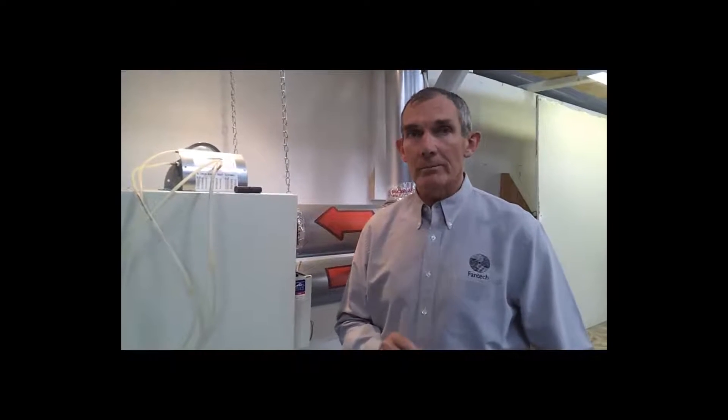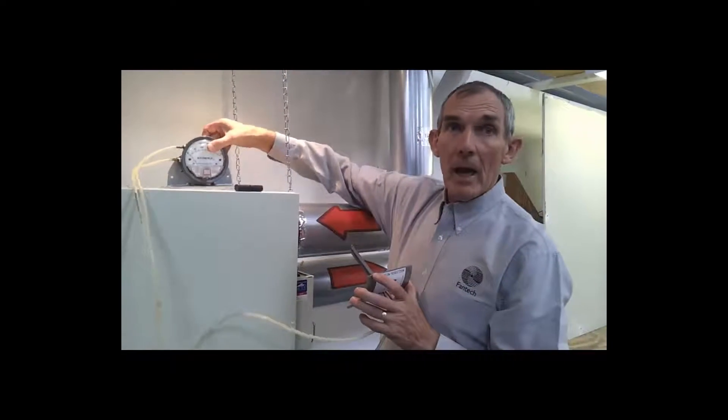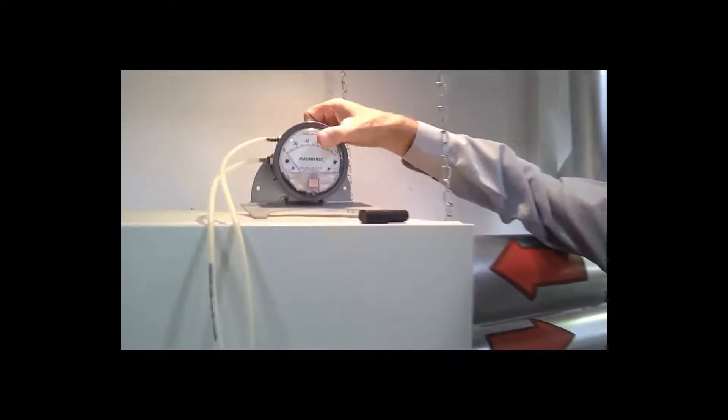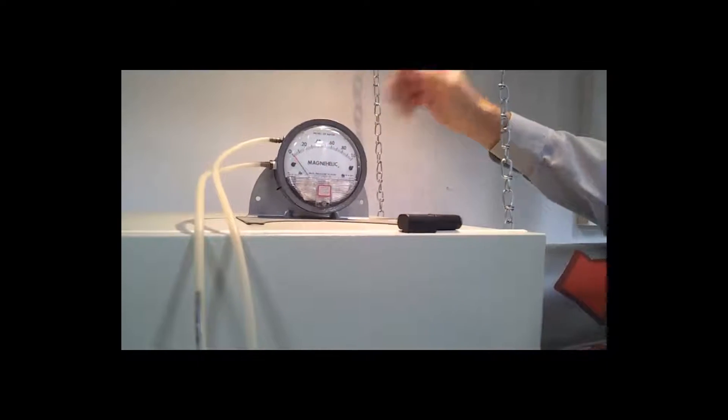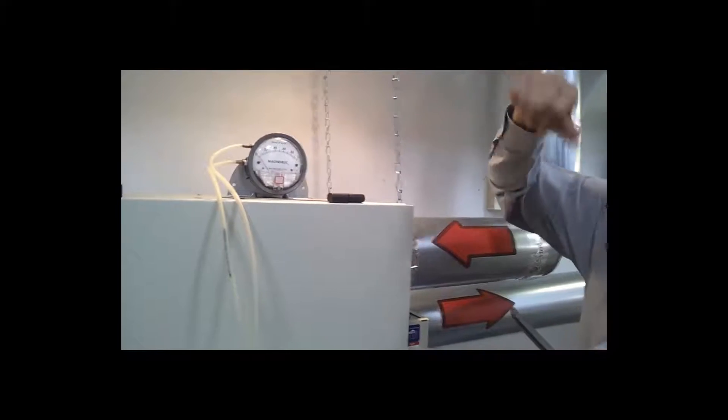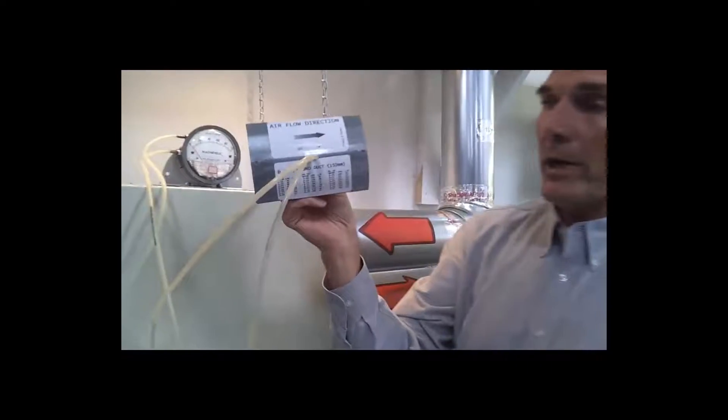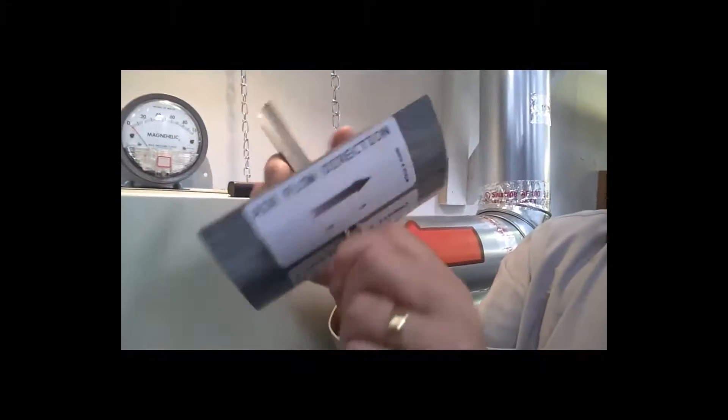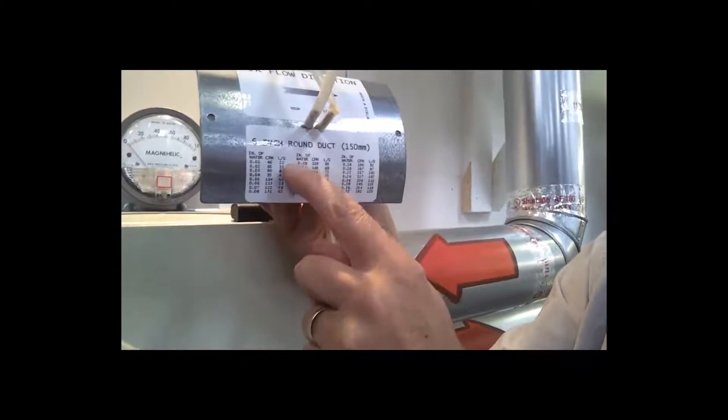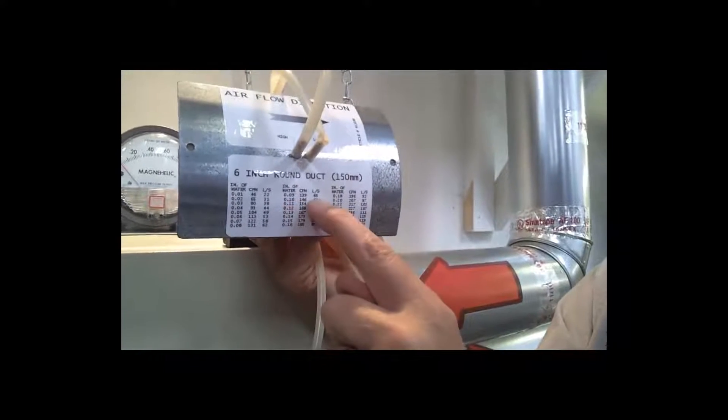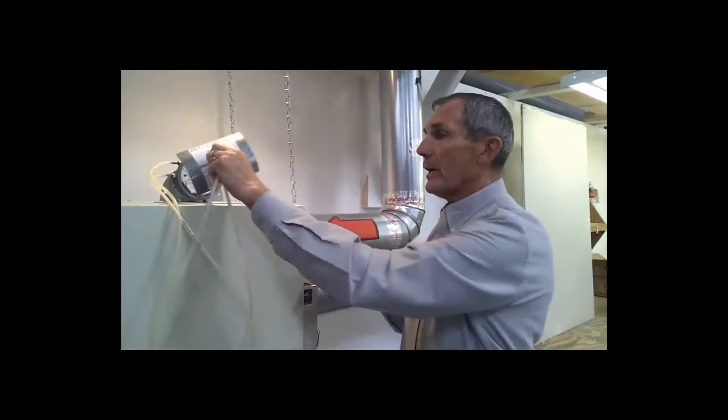Okay, the two things we're going to use to balance this system: we're going to use a Magnehelic gauge which you make sure is on a level surface, and a grid airflow insert. The good thing about this is you can read the pressure in the duct, and also it'll give you the air flow at that pressure.